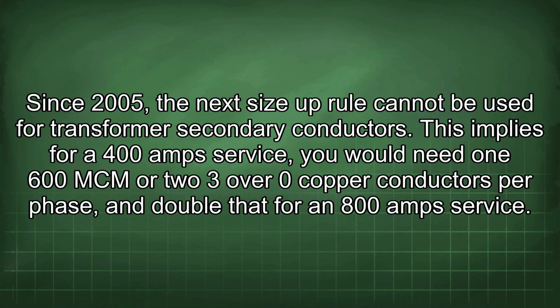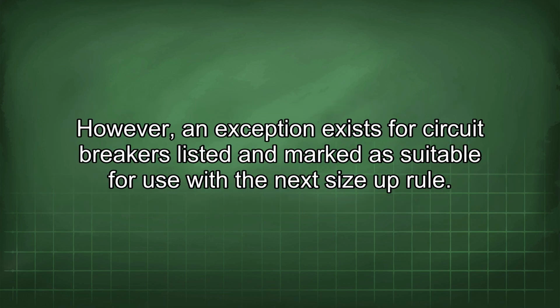Since 2005, the next size up rule cannot be used for transformer secondary conductors. This implies for a 400 amp service, you would need one 600 mcm or two 3/0 copper conductors per phase, and double that for an 800 amp service. However, an exception exists for circuit breakers listed and marked as suitable for use with the next size up rule.